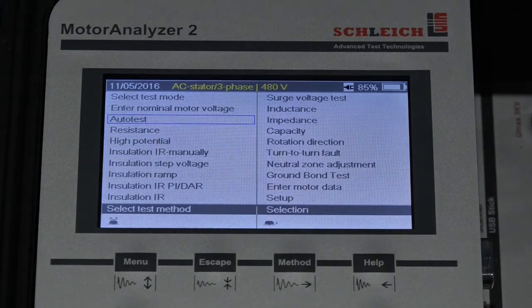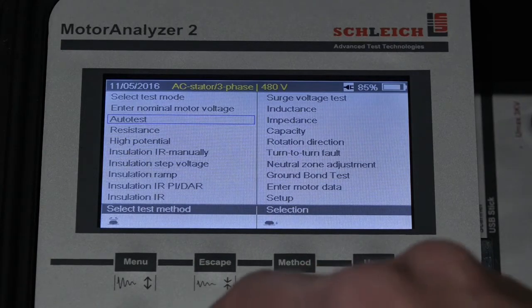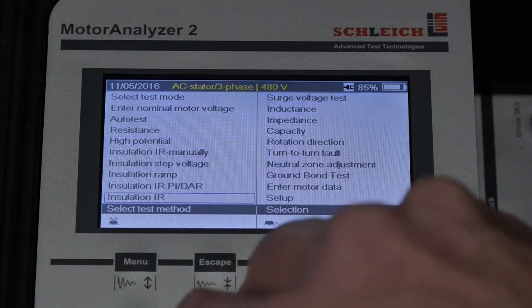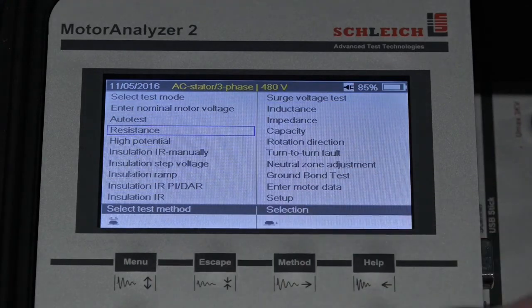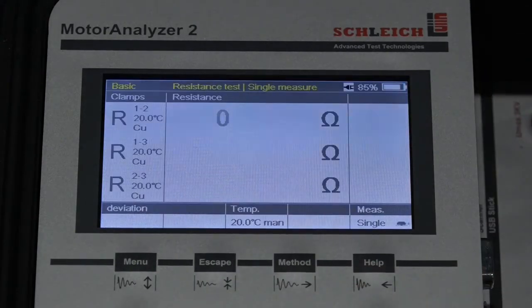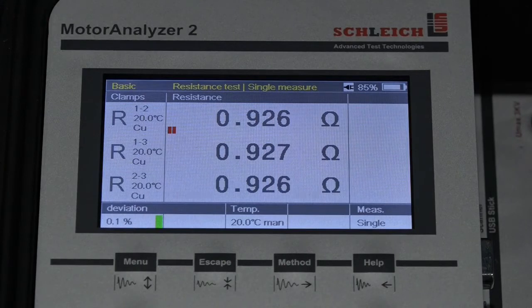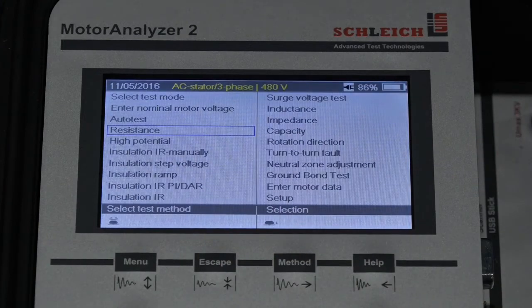So just to review, even though we have this automatic test capability that we showed earlier, we can still use this instrument much like you have in the past in the motor shop. Go direct to doing a DC high pot test, go direct to doing a surge test, and even if you want, we can go directly to running a resistance test. I'll just do that here. Select resistance, get the numbers, press the button. There you go, got 1 to 2. 1 to 3. And 2 to 3. So again, we can still run this test in a very normal mode that you've been used to using in a motor shop, but we get the added capability of a little bit of automatic control, controlling our test voltages and a little bit of the test sequence. We get very accurate, reproducible, and repeatable results.